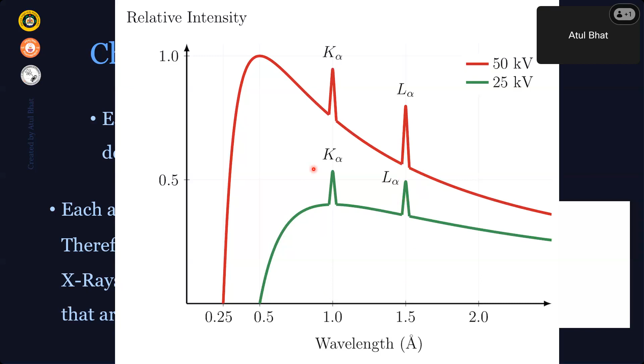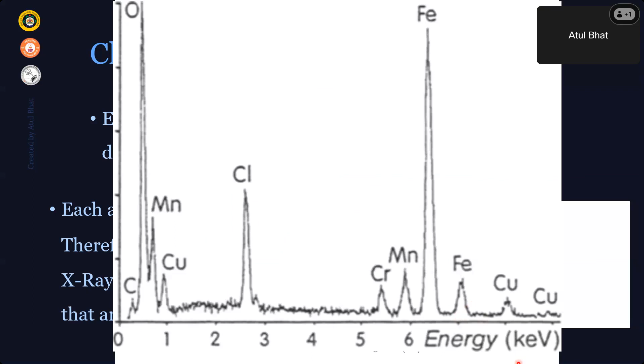So the peaks are exactly at the same point. For any given material, if you change the voltage, its intensity may increase, but these peaks are fixed at those points. That is why it's going to be the fingerprint. And this is how we find it. For any given material, these are the peaks we have. So if you have chlorine, you'll have a peak here at, let's say, 2.7 kilo electron volt, whereas oxygen would have it at 0.5 kilo electron volt. Iron, which I mentioned right now, is at 7 kilo electron volt. So by identifying where the peaks exactly occur, at which value of energy or wavelength, we can identify which material or which element is being used. Now, how do you do this experiment, and how do you find which element, and how did the element come into the picture?